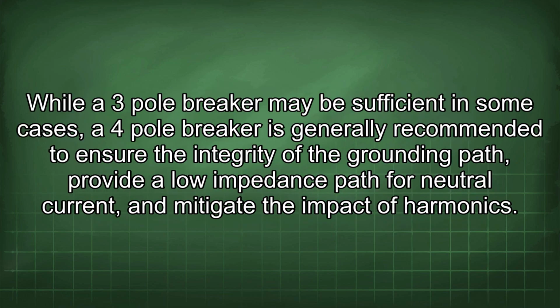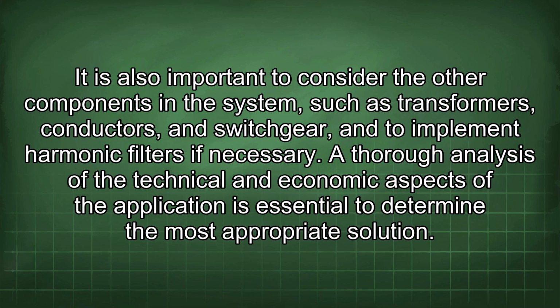While a 3-pole breaker may be sufficient in some cases, a 4-pole breaker is generally recommended to ensure the integrity of the grounding path, provide a low impedance path for neutral current, and mitigate the impact of harmonics. It is also important to consider the other components in the system, such as transformers, conductors, and switchgear, and to implement harmonic filters if necessary. A thorough analysis of the technical and economic aspects of the application is essential to determine the most appropriate solution.